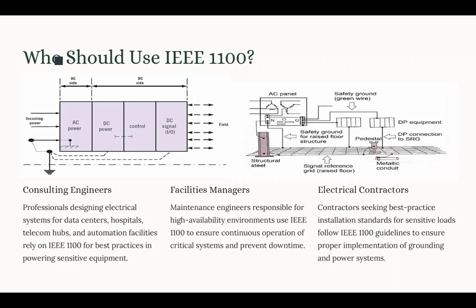Now, there is a periodic inspection of the signal reference grid, bonding network, interference, and the surge protective devices defined for facility managers in IEEE 1100, to make sure they remain within the operational specifications. Another aspect where this standard can help facility managers is load management. They can make sure the sensitive loads remain isolated from the noisy equipment. IEEE 1100 does that through zone segregation, which we are going to talk about in our upcoming slides. Now, if we have poor grounding or we ignore power quality issues, this ends up being the facility manager's responsibility. It's basically their responsibility to prevent those problems.